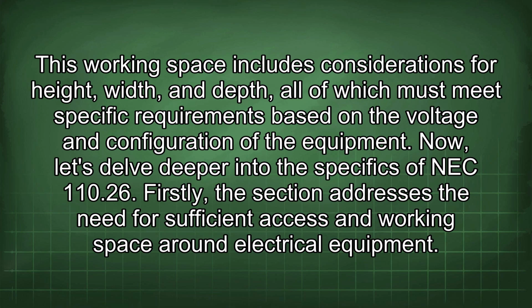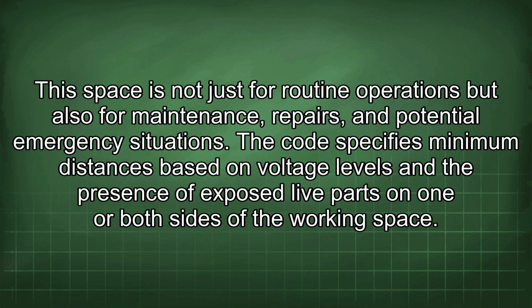Now let's delve deeper into the specifics of NEC 110.26. Firstly, the section addresses the need for sufficient access and working space around electrical equipment. This space is not just for routine operations but also for maintenance, repairs, and potential emergency situations. The code specifies minimum distances based on voltage levels and the presence of exposed live parts on one or both sides of the working space.